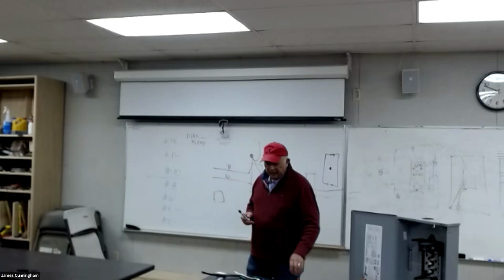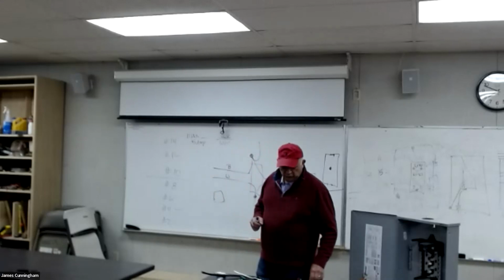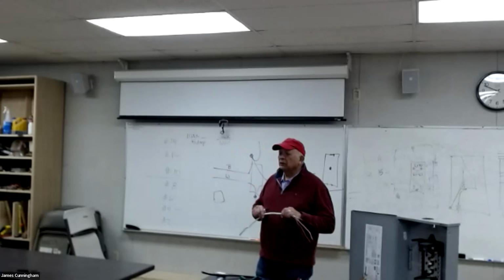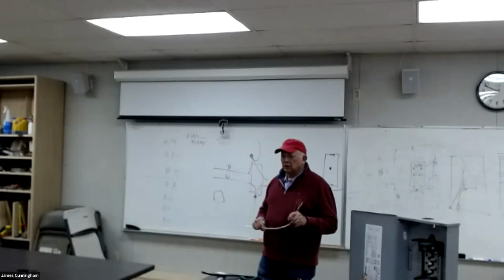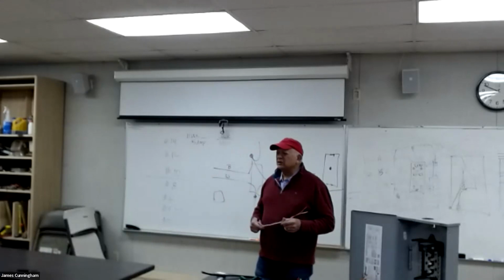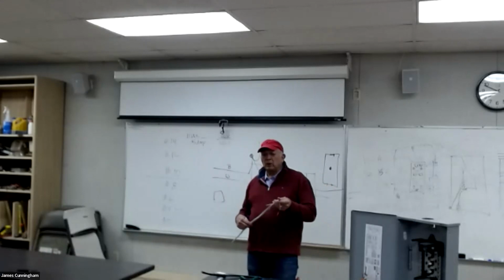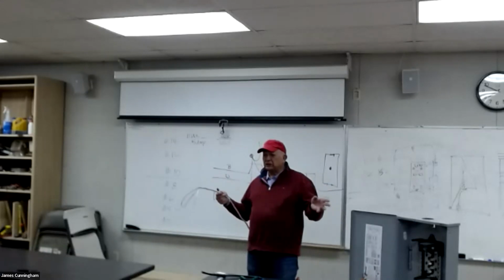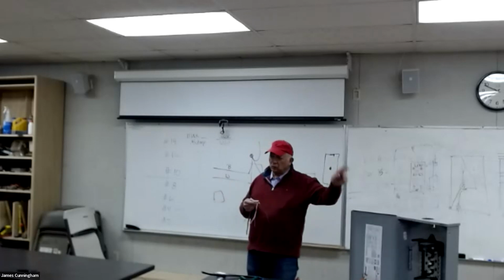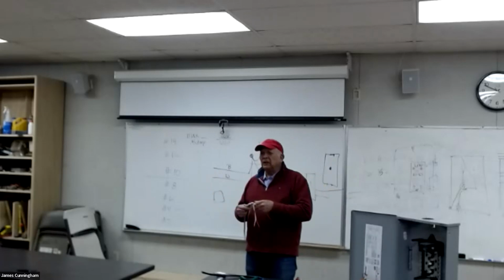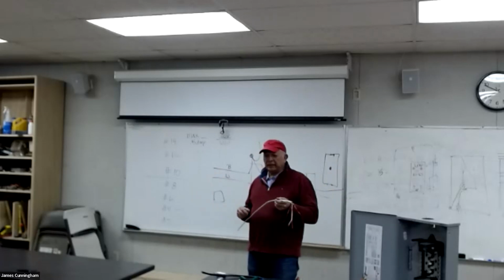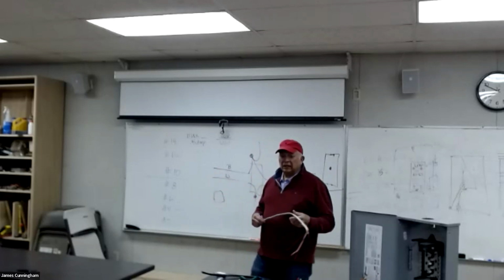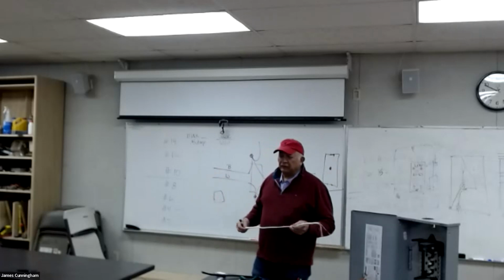Also, remember that we used to be able to do 2 circuits on 3-wire Romex. We can't do it anymore with the arc fault circuit interrupter plugs. It'll pop if you try to do that. We used to do it all the time. It would save on wire. You use one 3-wire Romex, and I could do 2 circuits, 2 bedrooms, run one circuit to one bedroom, run the other circuit to the other bedroom. And if the house was long, you'd save 50 feet of wire.